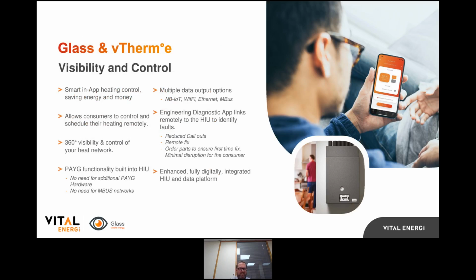I said at the start that Glass has much wider capabilities than a standard metering and billing platform. Well, this is where it really starts to hit home. Glass can be built into our vTherm range of HIUs. When Glass is linked to a vTherm HIU, it brings Hive-like capability for that consumer. The consumer can schedule their heating timescales and routines. They can also turn on the device remotely from the park, from the pub. They can turn it off if they've gone on holiday and forgot to turn the heating off. They can do all that remotely, so it brings that Hive-like capability and control.